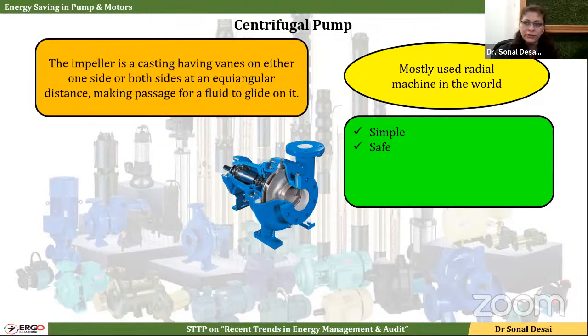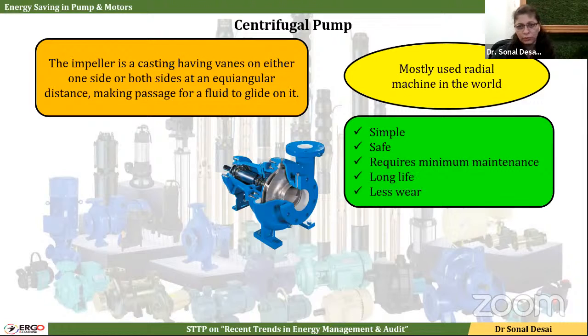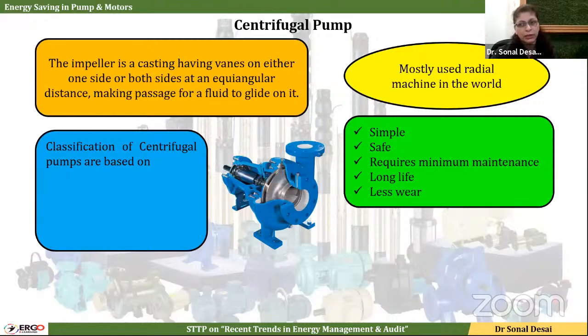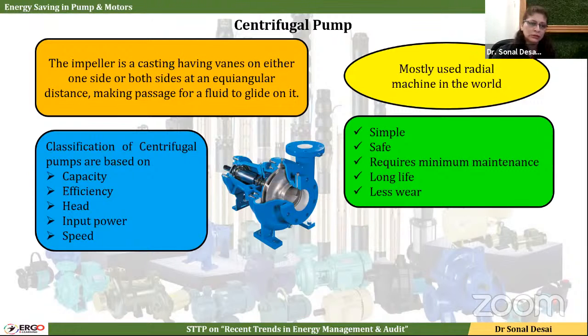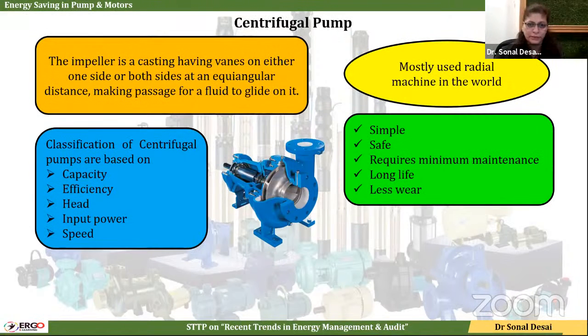We normally select a centrifugal pump for almost all applications because it's simple. It has a minimum of working components. It requires less maintenance, has a longer life and is durable, and wear and tear issues are less. So looking at all these feasibilities, a centrifugal pump is normally selected, though its efficiency is not very high, but it is good to use. And they are further classified based on capacities, efficiency, head handled, input power given, speed at which it is running, or type of impeller.